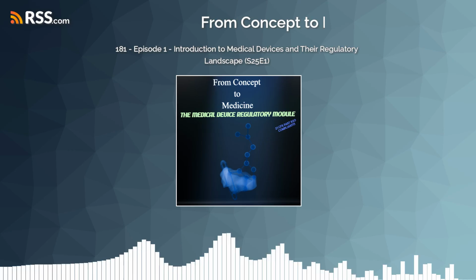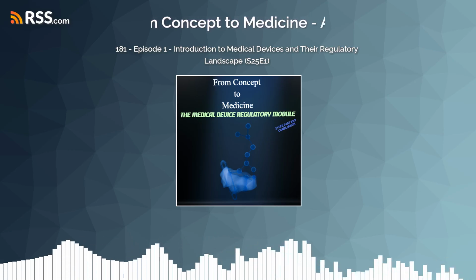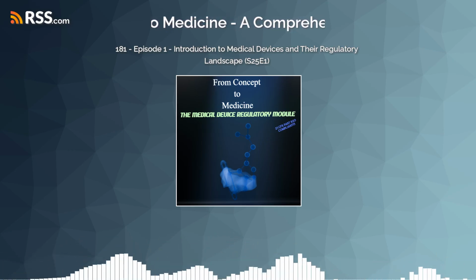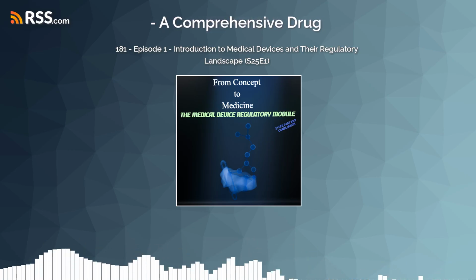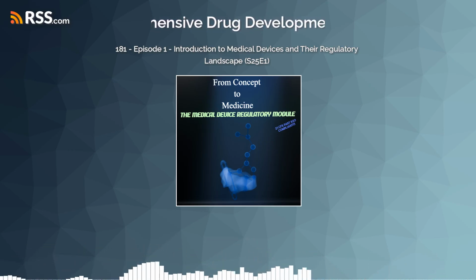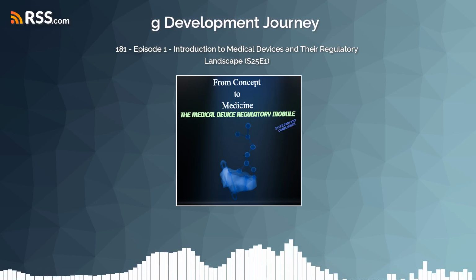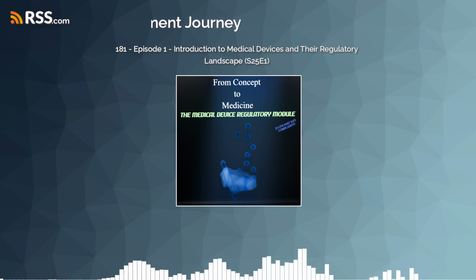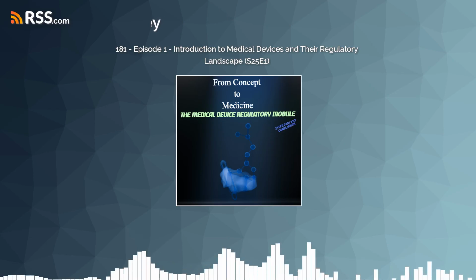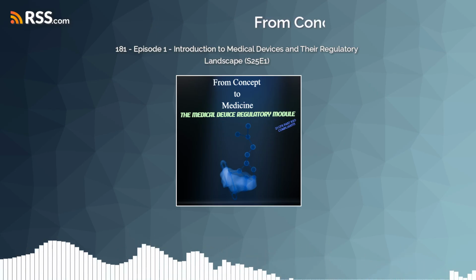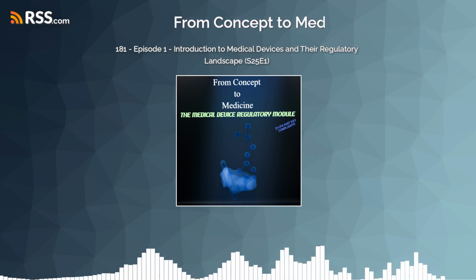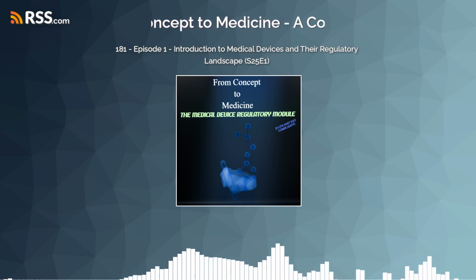Right. But the story of patient safety doesn't end when the device gets approved or cleared, right? The FDA's commitment to quality must extend throughout the entire life cycle. Absolutely, it has to. And that's where the Quality System Regulation, or QSR, comes back into play in a big way. That's 21 CFR Part 820 again. The device CGMP. Exactly. It serves as the equivalent of current good manufacturing practices, but specifically for devices.